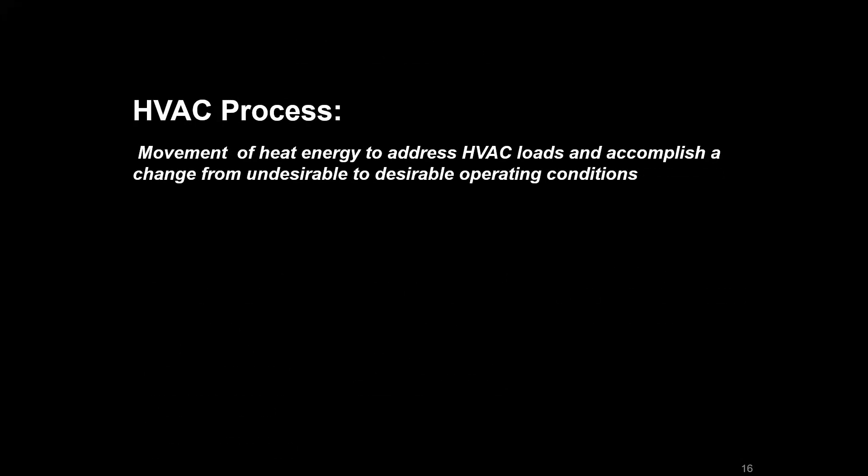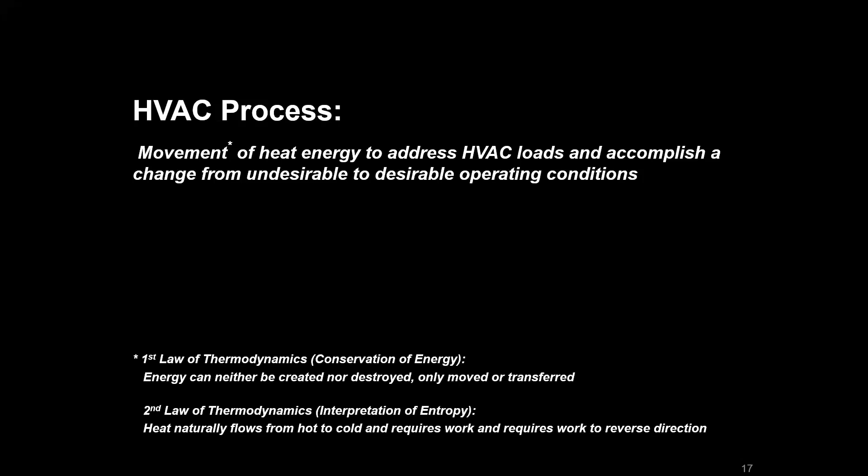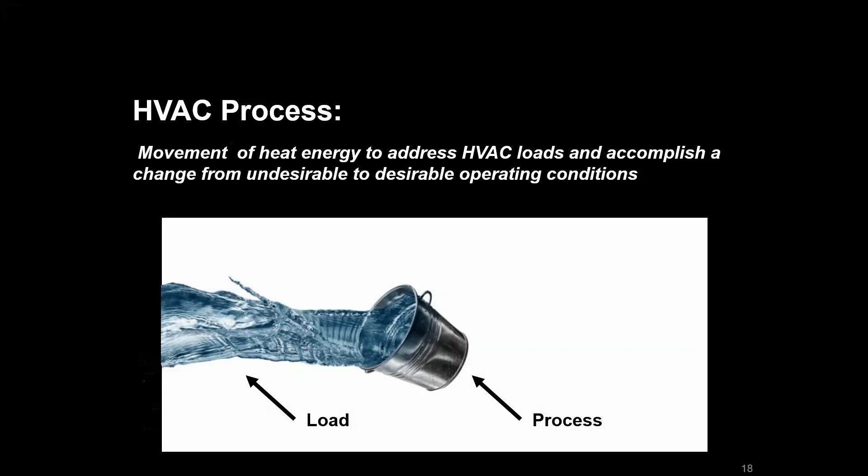The HVAC process really is just the movement of heat energy in order to address these loads and accomplish a change from a state where you don't want to be to some comfortable, design, or mission operating condition. We use the term 'movement' to be in line with the first law of thermodynamics, which tells us we can't create or destroy heat energy — we can just move it from inside the space to somewhere we're less concerned about, like outside. And per the second law of thermodynamics, this is going to take some work to accomplish. A more simplistic way of thinking about this: if you're in a rowboat with water coming in, you take a bucket and chuck that water out. In that case, the water is the load and the process is the bucket and the act of hurling that water out of the boat.